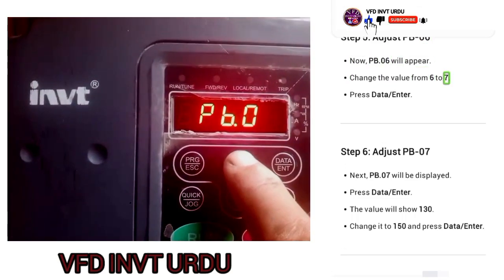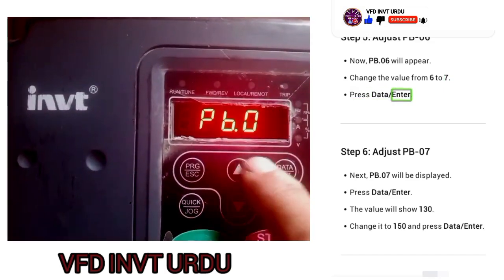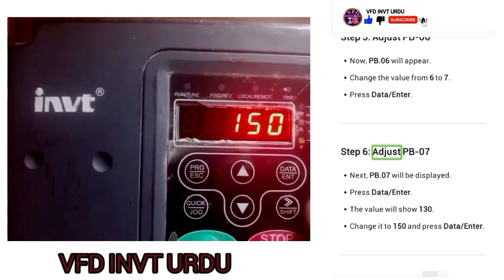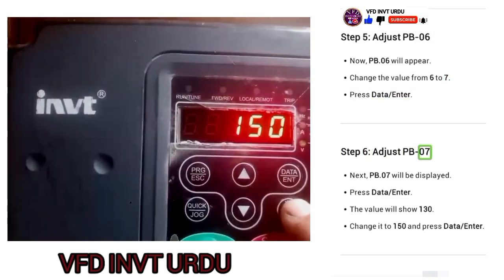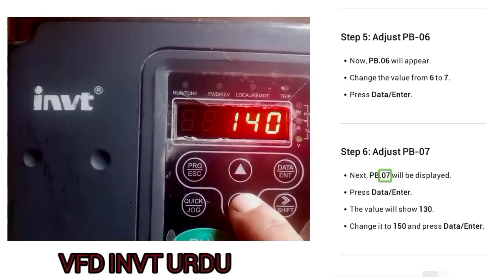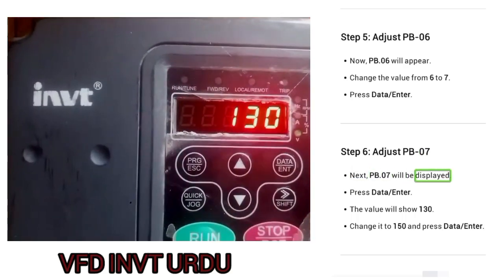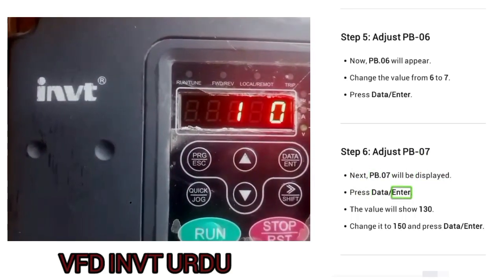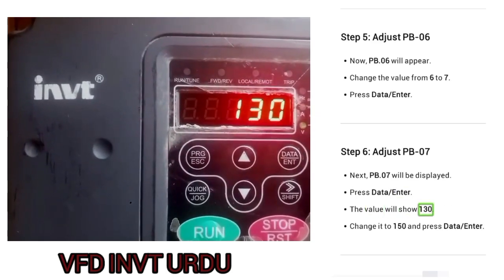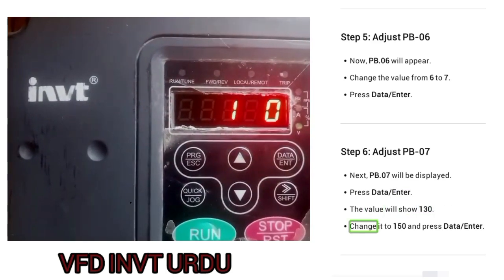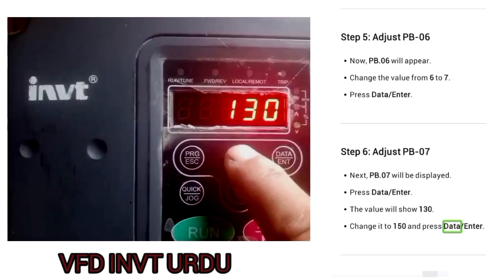Change the value from 6 to 7. Press data enter. Step 6. Adjust PB-07. Next, PB.07 will be displayed. Press data enter. The value will show 130. Change it to 150 and press data enter.